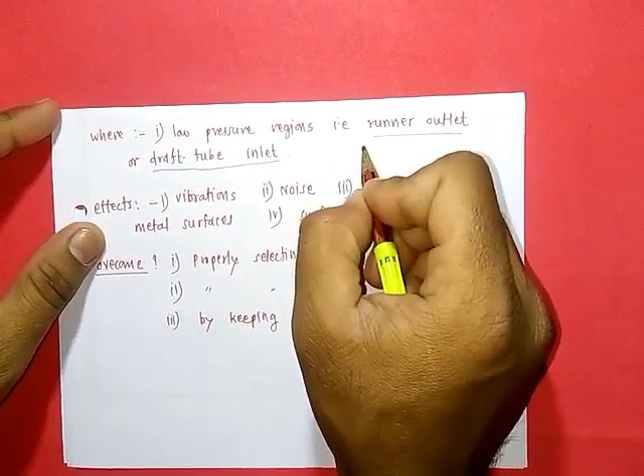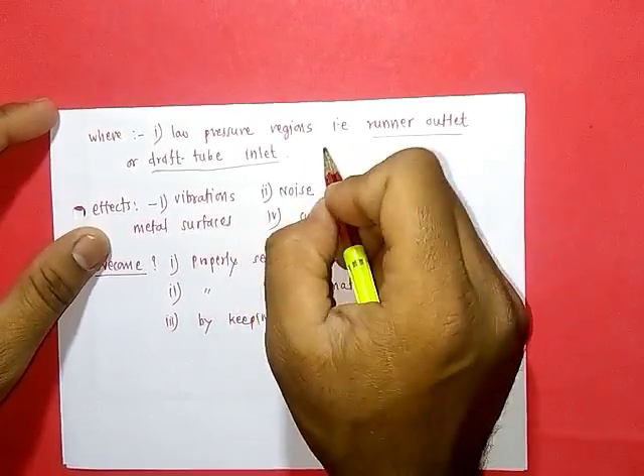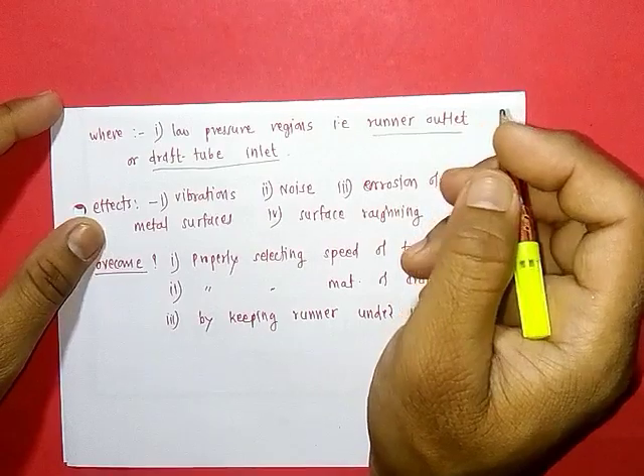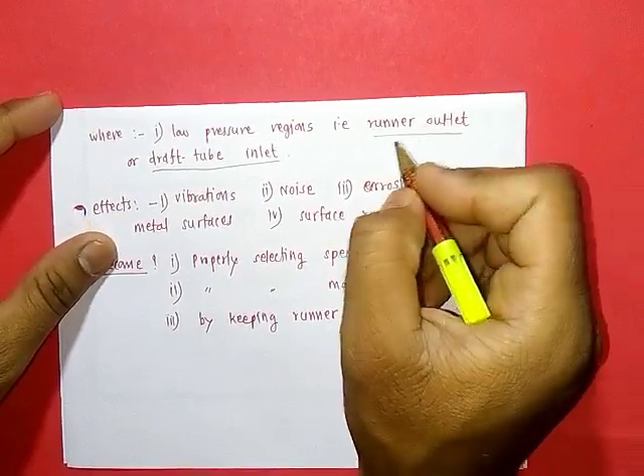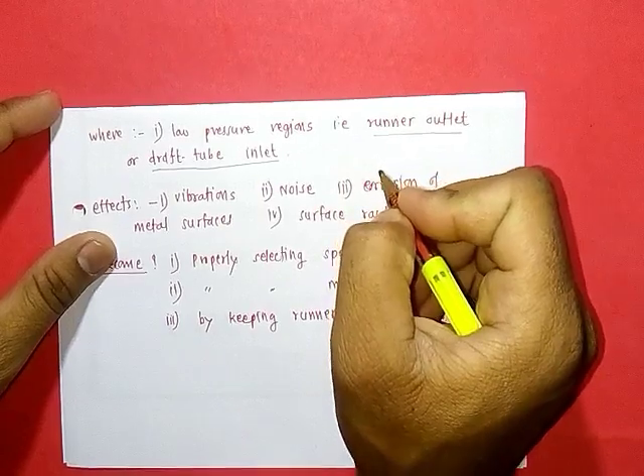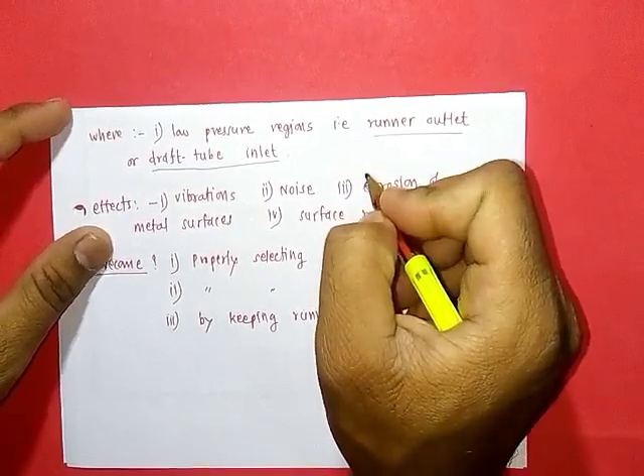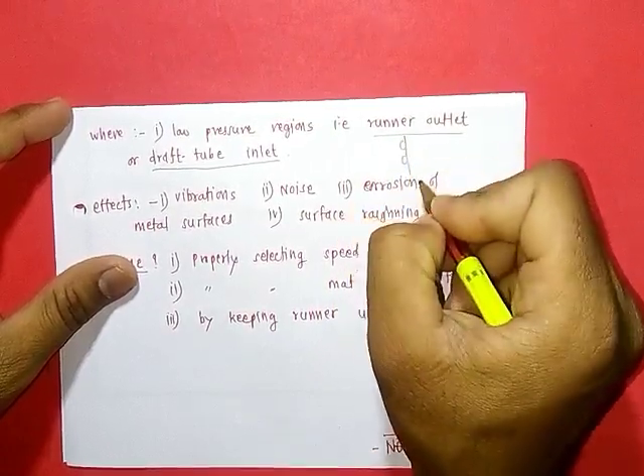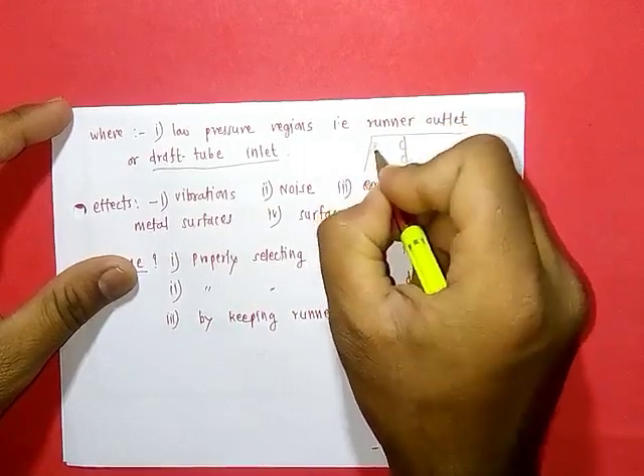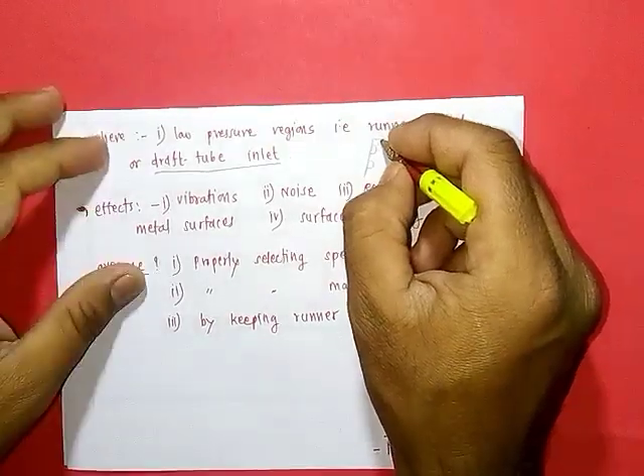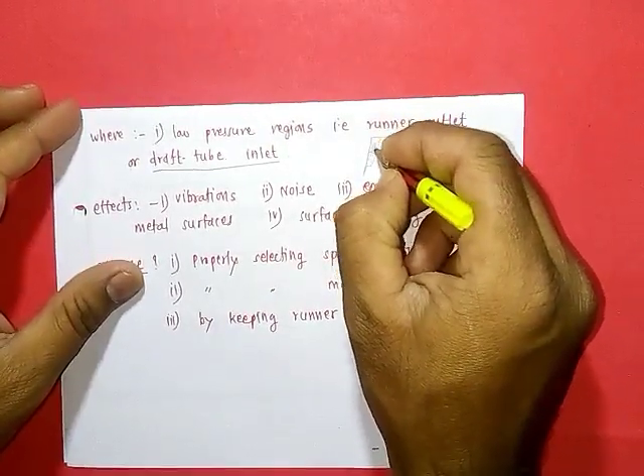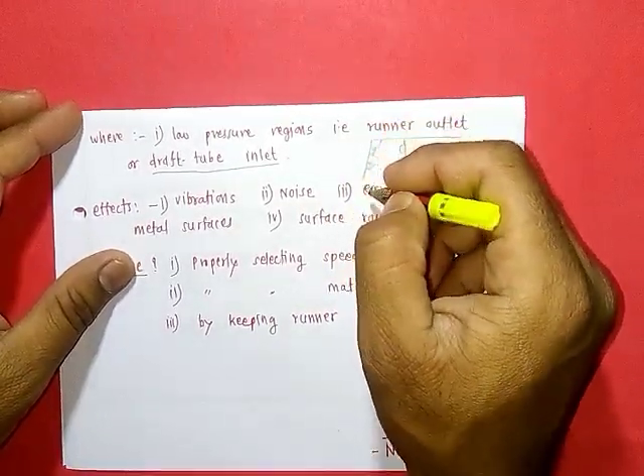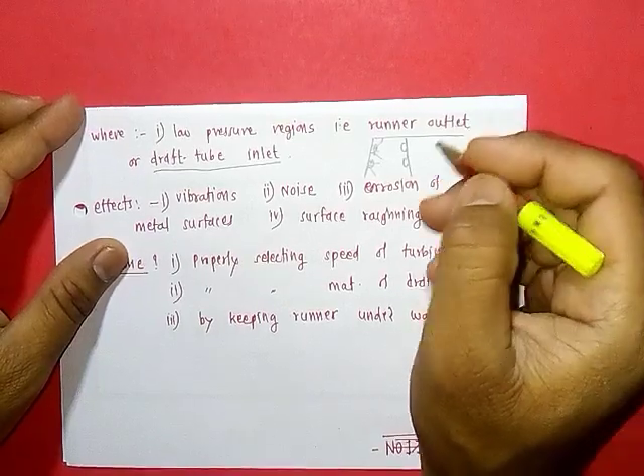As the bubbles flow to high pressure regions, the pressure inside the bubble is low while the surrounding pressure is high. Due to this pressure difference, the bubbles collapse. When these bubbles collapse near the walls of the draft tube, the hammering effect of surrounding water on these empty or vapor-filled regions causes the surface of the draft tube to get eroded and roughened.